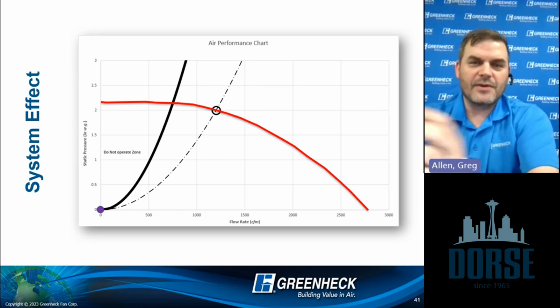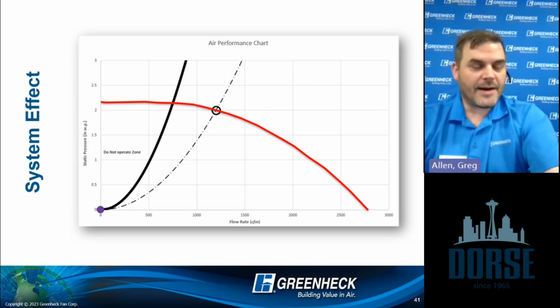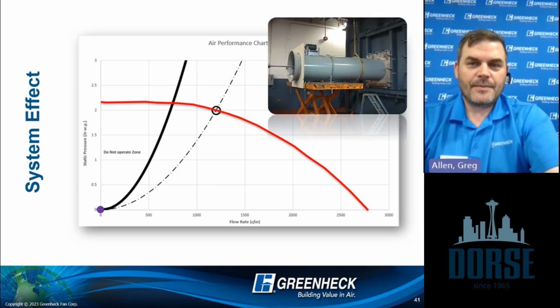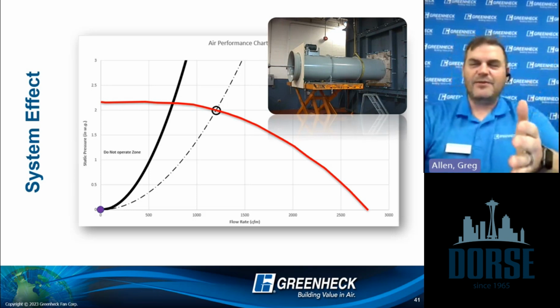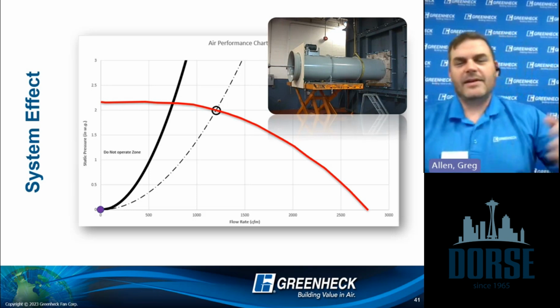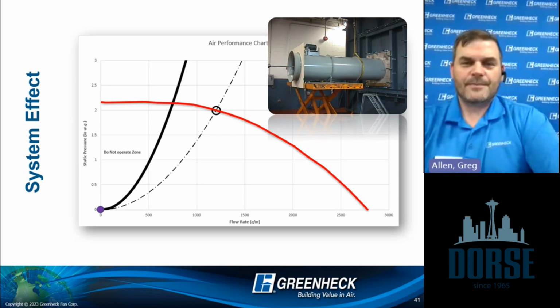It was a beautiful curve. It was in an efficient point of operation in this fan's capabilities. Perfect. That's how I tested this fan. That's how I got all this data. And mind you, air moves into the fan beautifully smooth. It exits beautifully. Everything's gorgeous.